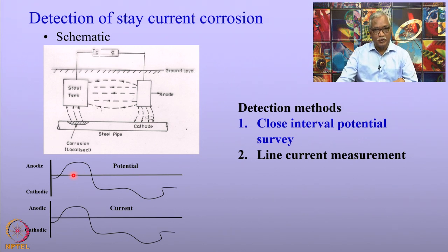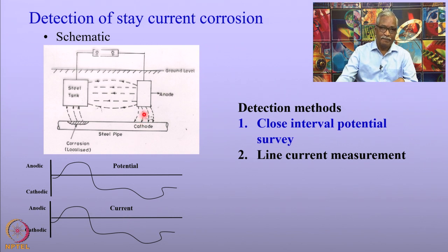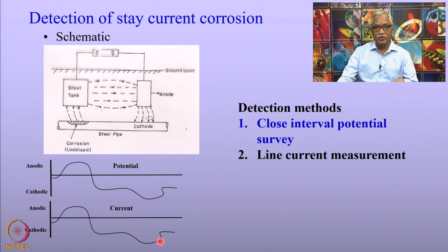It is also possible to measure the line current. In the schematic, the line current between two segments of the pipeline shows more cathodic current at the location where the stray current is collected by the pipeline, and then the current turns anodic where the current leaves the structure. So it is possible to detect stray current corrosion using two simple techniques — close interval potential survey and line current measurements — with the close interval potential survey being the simpler of the two.